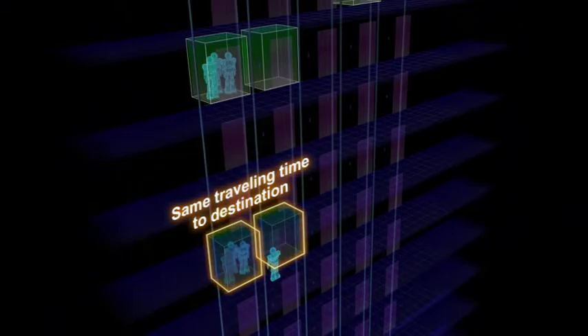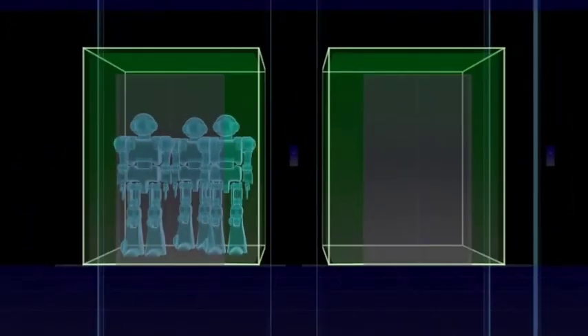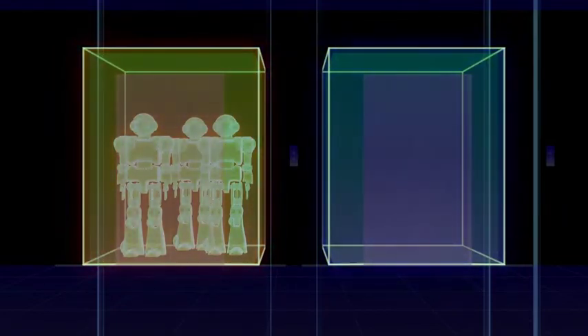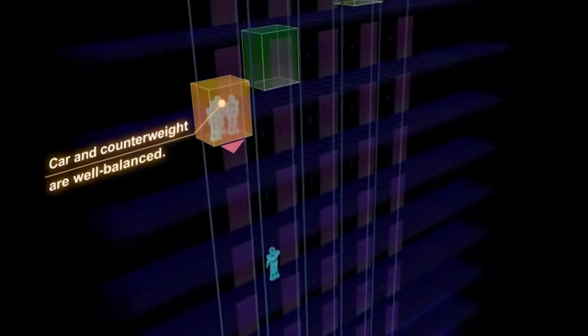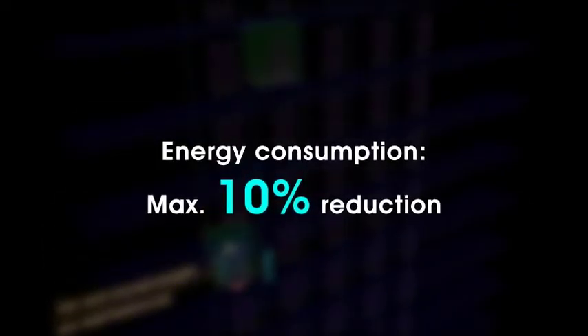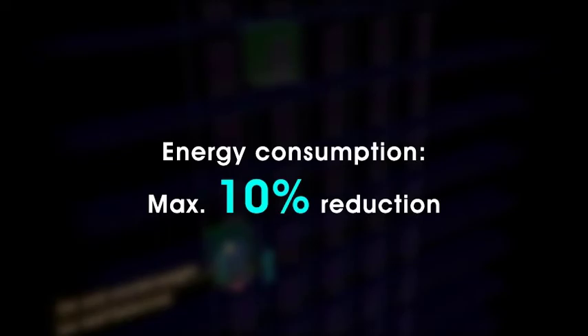If it takes almost the same time for these two cars to reach the target floor, this left car carrying passengers is assigned as the car is able to descend with less energy consumption. This function can reduce up to 10% in energy consumption without sacrificing passenger convenience.